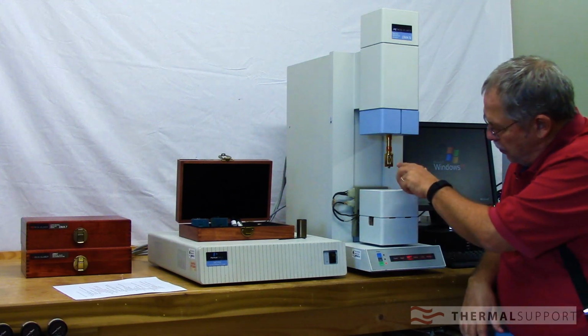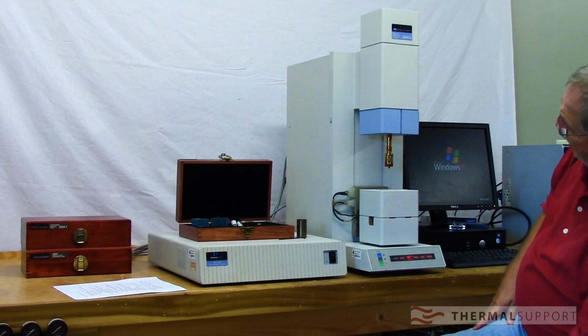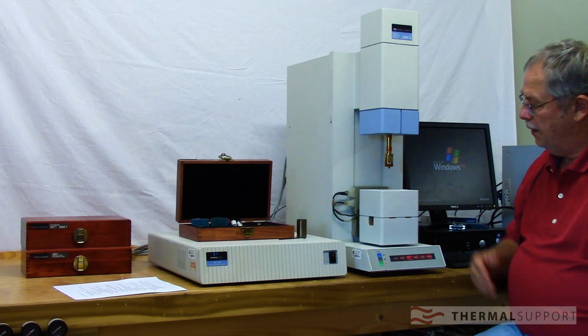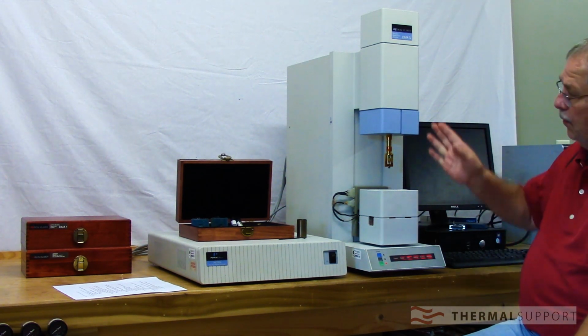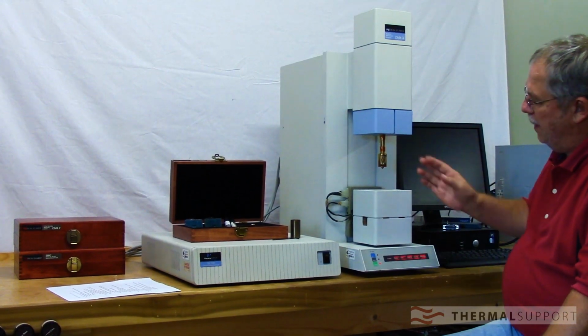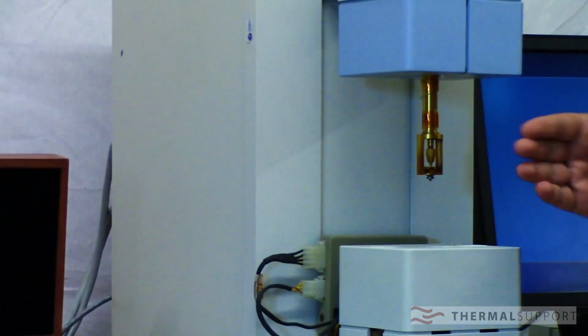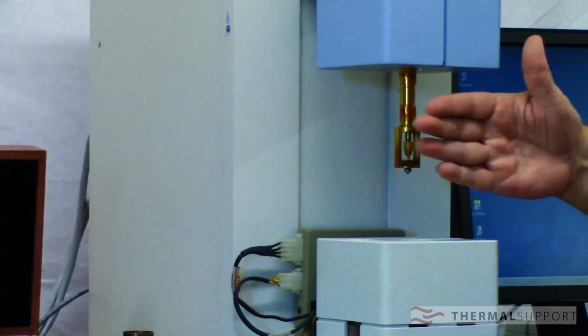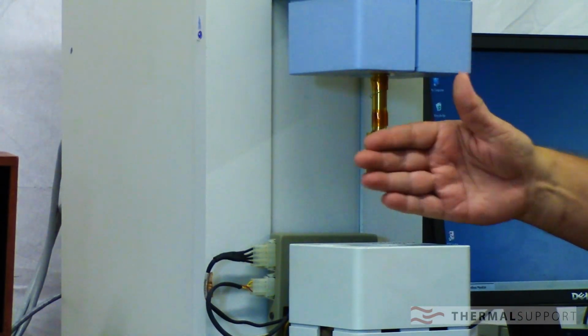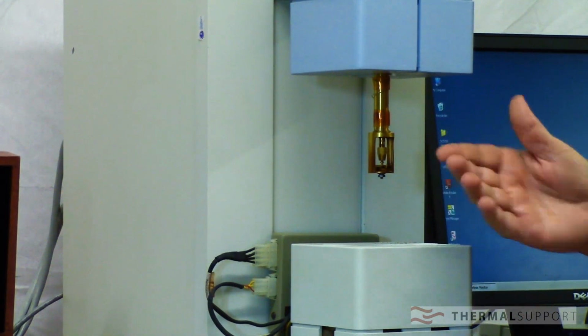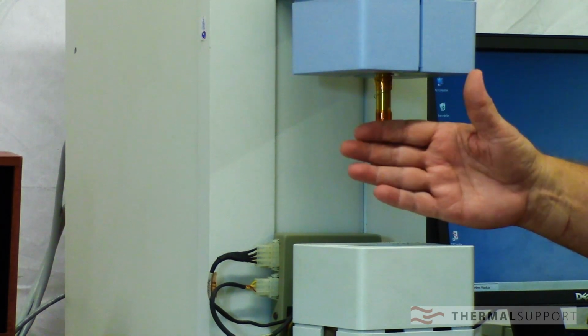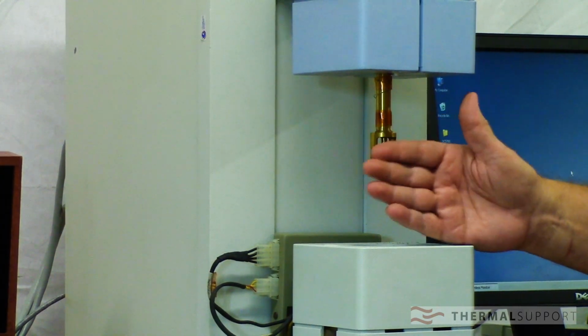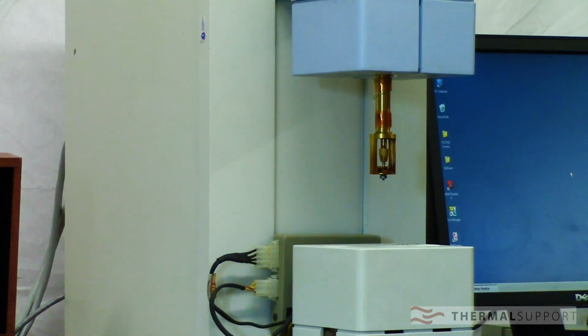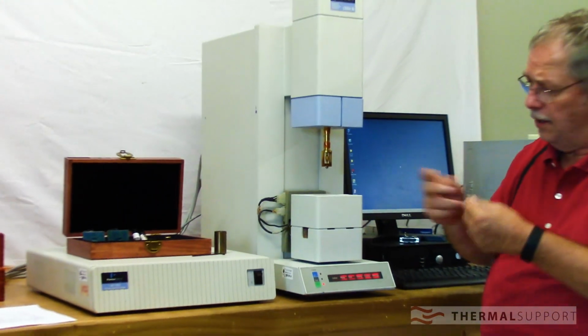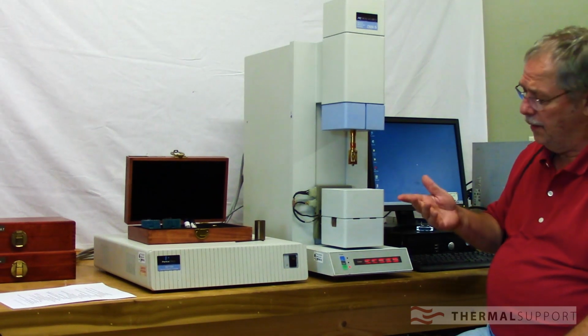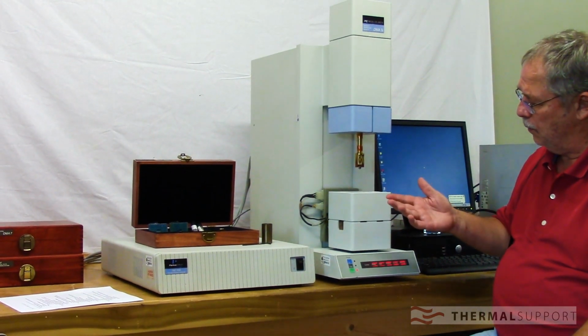When you turn on the analyzer, the probe should pop up a couple millimeters, probably. You'll see where the motor is keeping this probe right now. If it's at a little bit of an angle, you can always turn this, or you can adjust the sample platform so you don't have to take it all apart. Or if you want to keep the sample platform in a particular place, you can take the probe off and adjust the head like I told you a little bit earlier.